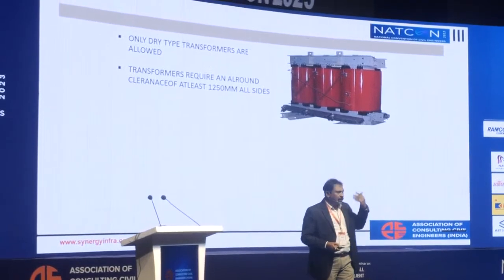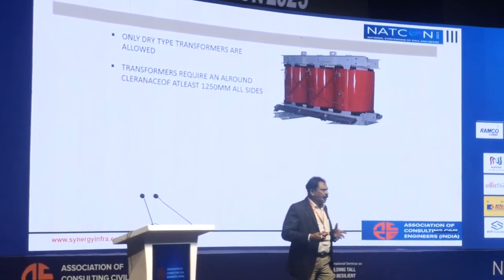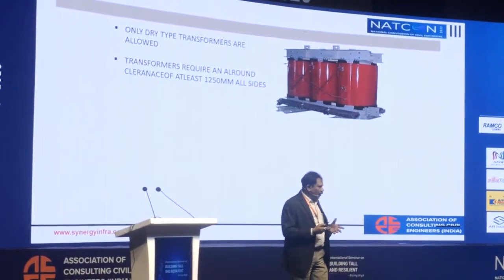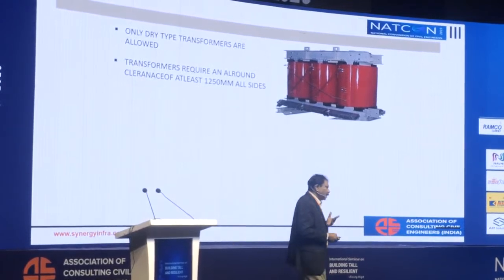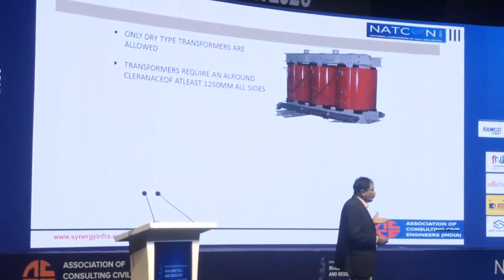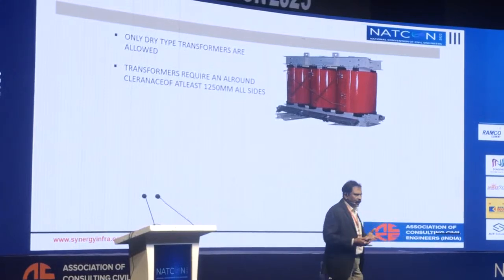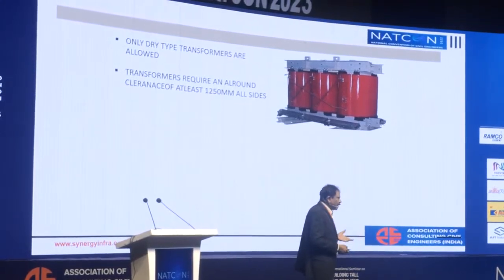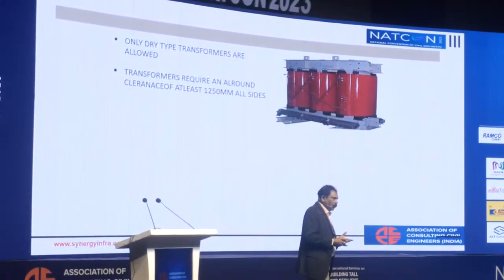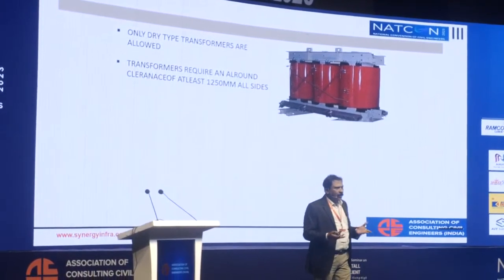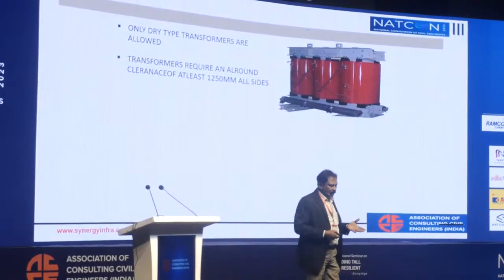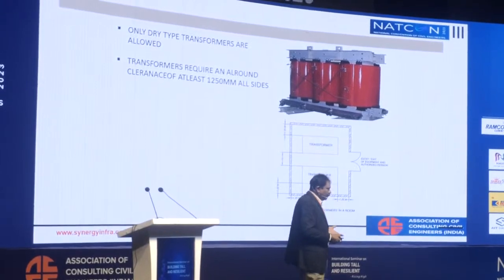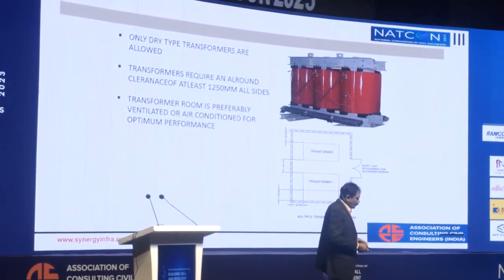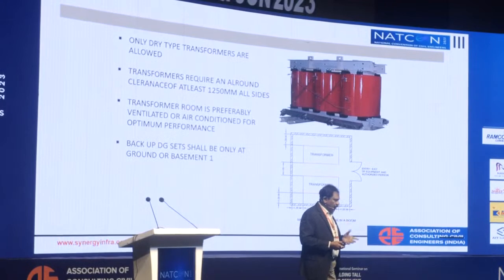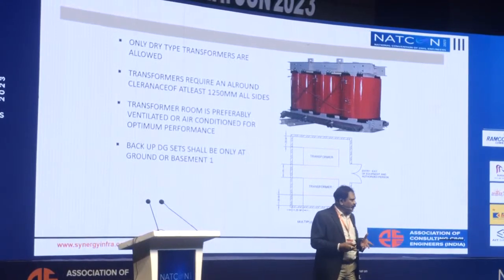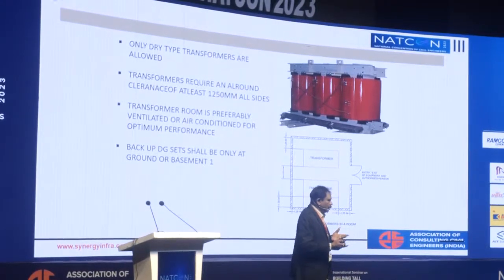We can provide transformers even at higher levels. Any commercial building usually will have a lot of air conditioning loads and other things, so it may be worthwhile to have a transformer at upper level, maybe at the terrace or wherever the AC plant is located. Whereas for other types of buildings, depending on the load, we can look at a techno-commercial analysis, whichever is right, which is beneficial for the project. And then a transformer should have the required clearances and other things. They are all the same, either at ground or at upper level.